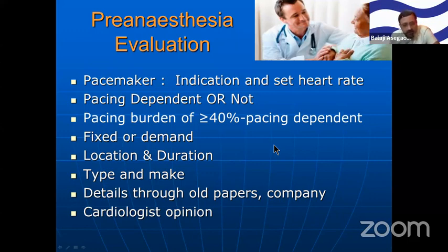Now see the location and duration of the pulse generator. Where it is located is very important when you want to use a cautery with that pacemaker. And how long has it been in place? Why do you want to ask the duration? To gauge the battery life of that pacemaker. That is why, as an anesthesiologist, you need to ask the duration.